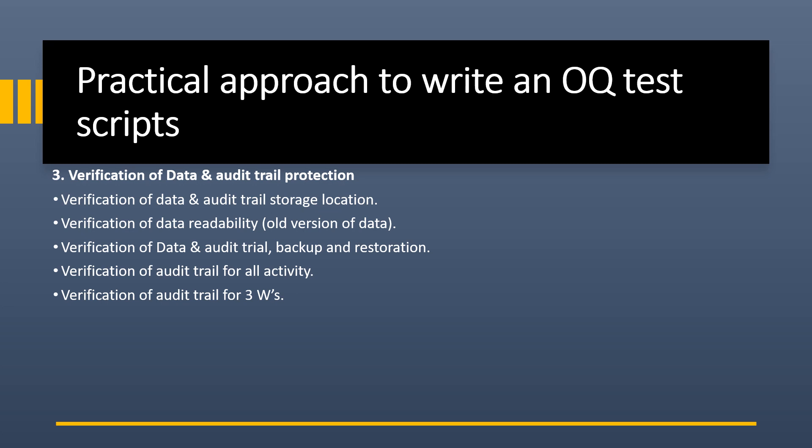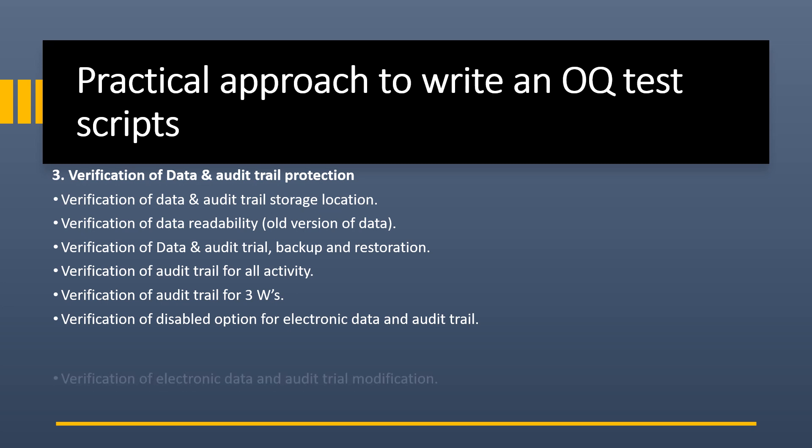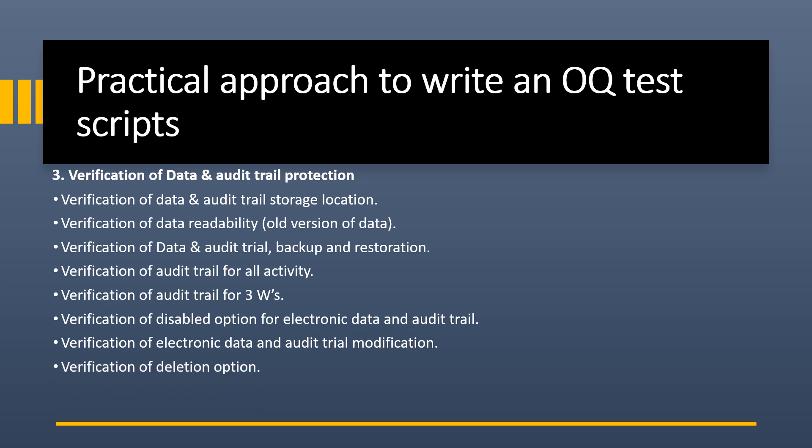Next is verification of disabled option for electronic data and audit trail — there should be no option to disable generation of electronic reports or audit trails. Next is verification of electronic data and audit trail modification — data and audit trails generated by the system should not be editable. Next is verification of deletion option — no one should be able to delete any data or audit trail.